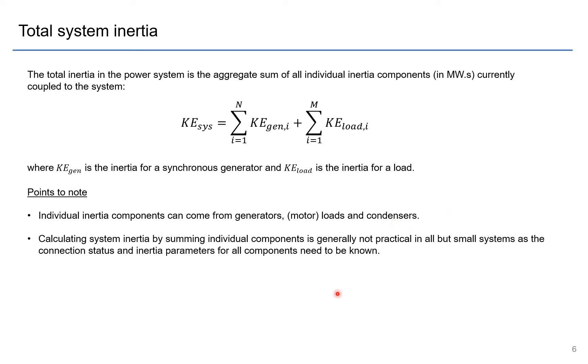Now calculating the system inertia by this method of summing up all the individual components is generally not all that practical in anything but very small systems where the connection status and the inertial parameters for all the components are known. And we'll get to this a bit later on in the estimation of inertia, but suffice to say that it is difficult in large systems particularly to estimate what the load inertia in the system is.